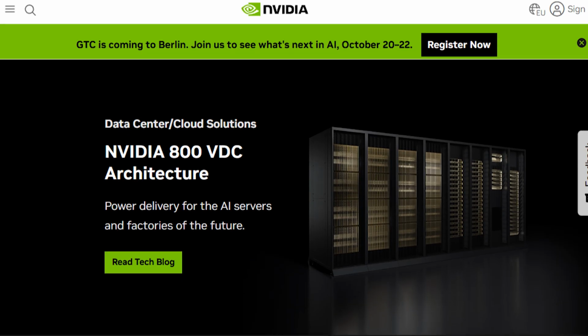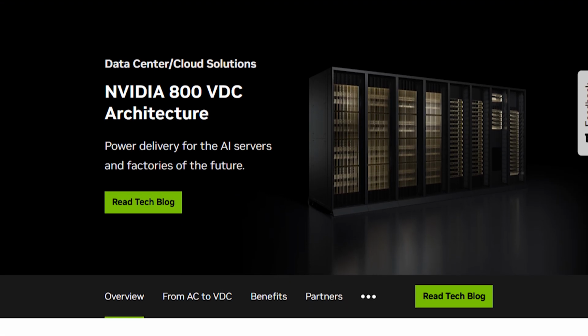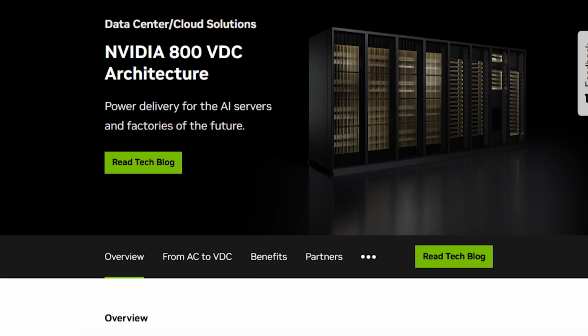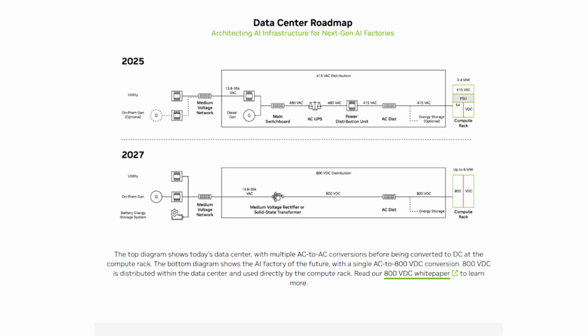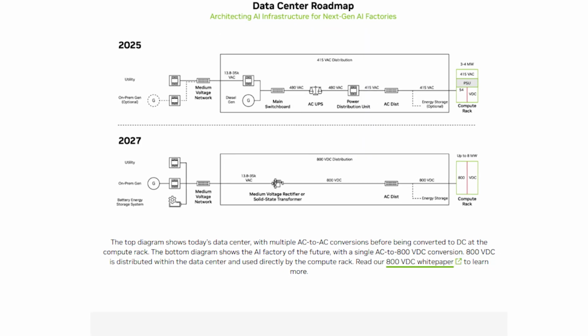A technical reference I want to give is that NVIDIA is developing an 800 volt DC architecture for future AI data centers, with the stated objective of around 1 megawatt IT racks from the beginning of 2027. This is a future architecture to which the industry is going to shift. Even though it's not a stated mandatory standard, it's an architecture onto which the industry is going to move and adopt.